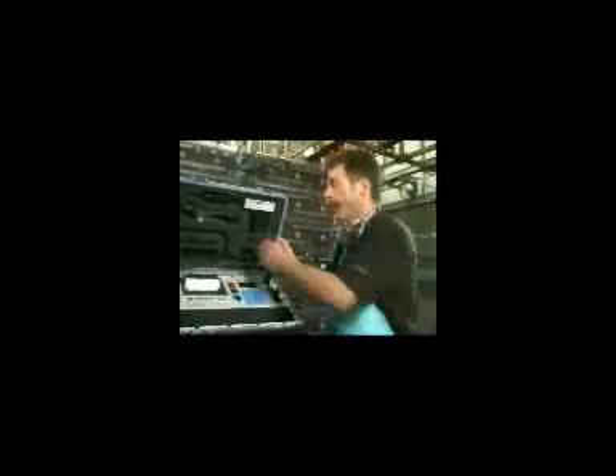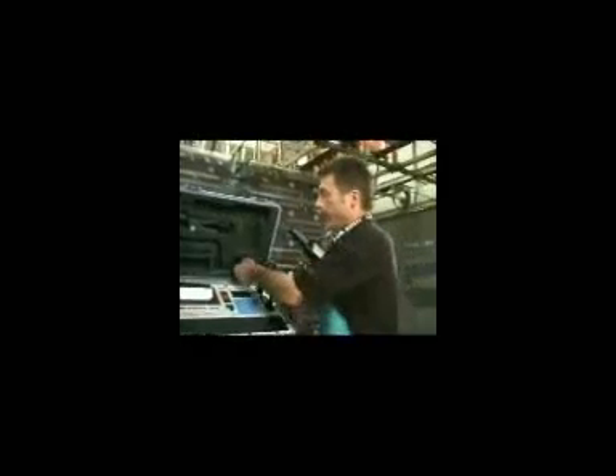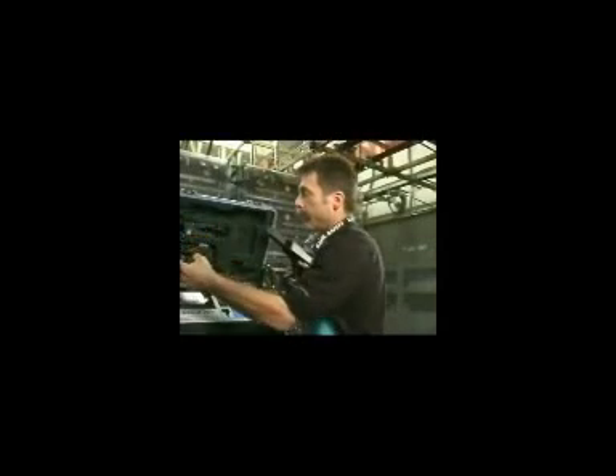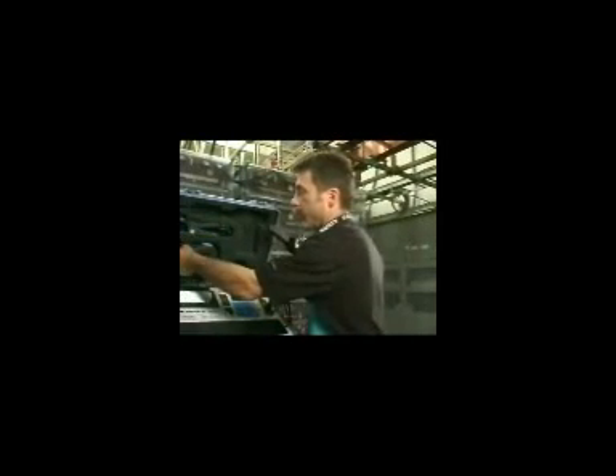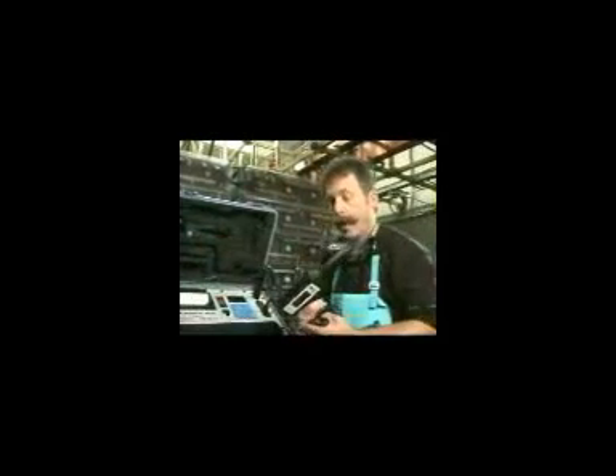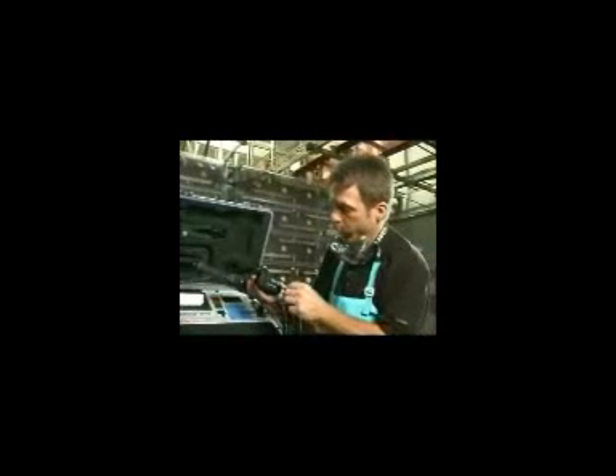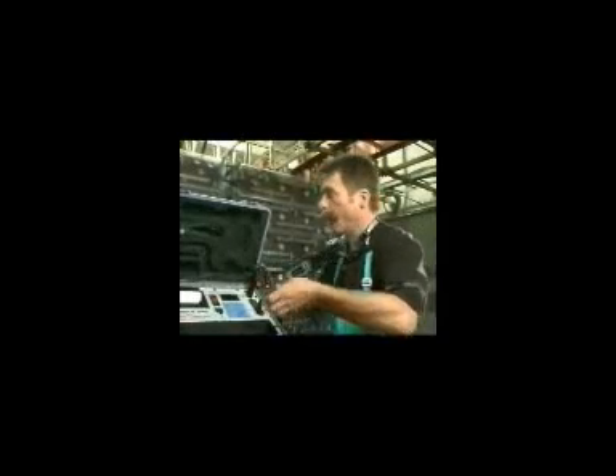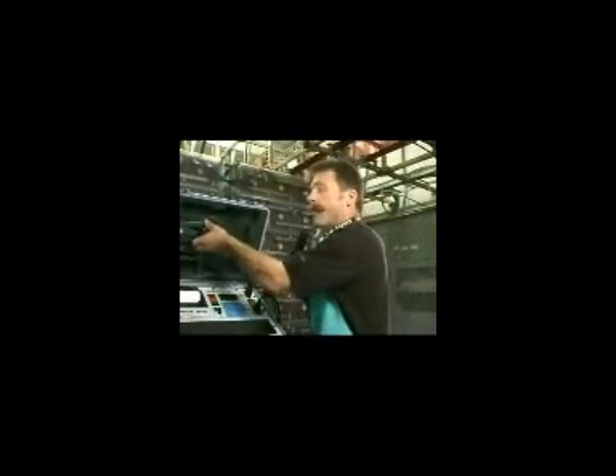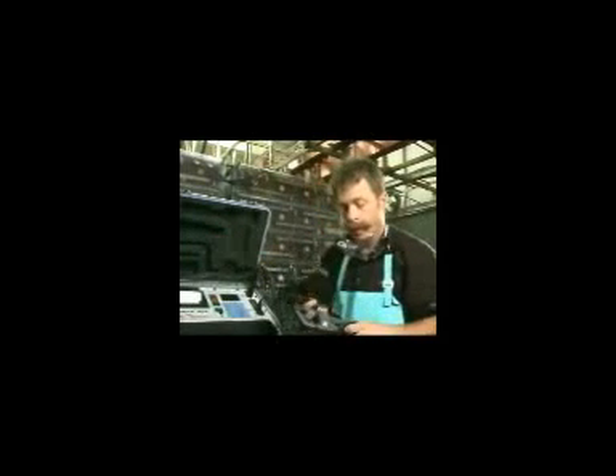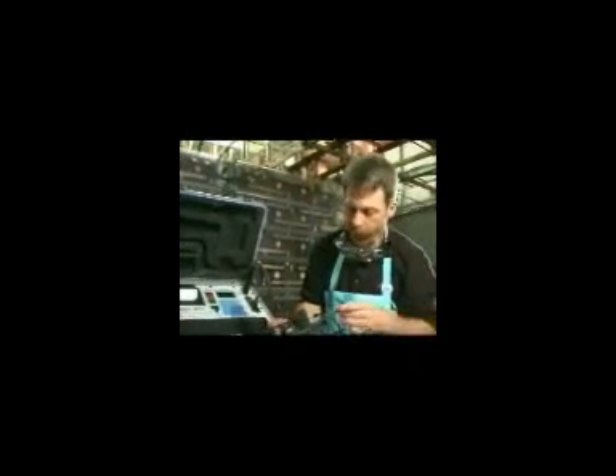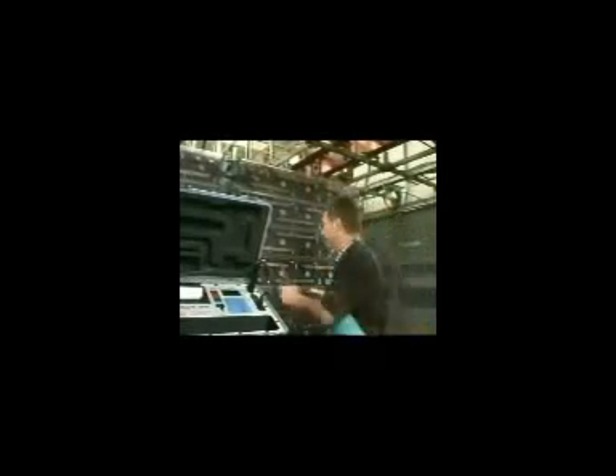And now we're going to make the receiver connections. The receiver, the potential probe, has a keyed gray connector that goes into the bottom of the receiver, and also our CT, which is used to measure the current in a battery string. That's also a keyed connector that goes into the bottom of the instrument. We're going to make this connection on the inter-tier cable, and after I put my safety gear on, we'll be ready to take measurements.